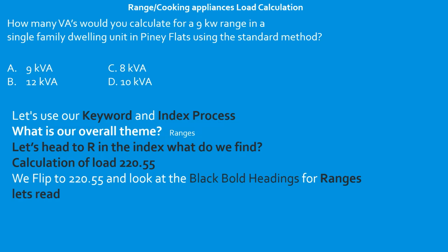Let's give you a little tip about finding tables while we're right here. If you read in the paragraph under a black bold heading and it says that you're allowed to use a table, or it directs you to use a table, what you're going to do is you're going to look at the surrounding tables. It's going to be within a couple pages. So let's look to the left here. It says Table 220.42. That's not right. We're looking for 220.55.